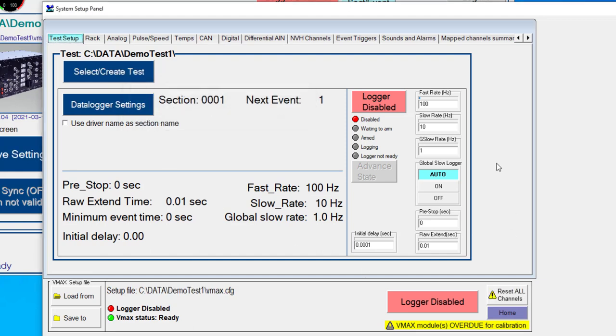Okay, now on this screen, we have some of our basic logger settings. We have three different sample rates that we can select. We have our fast rate, which is what you would collect most of your signals at typically. In this number, by default, our as-ship software is limited to 1000 hertz.